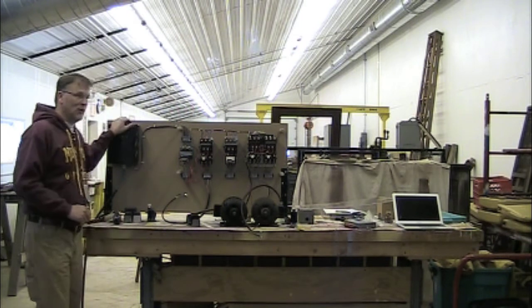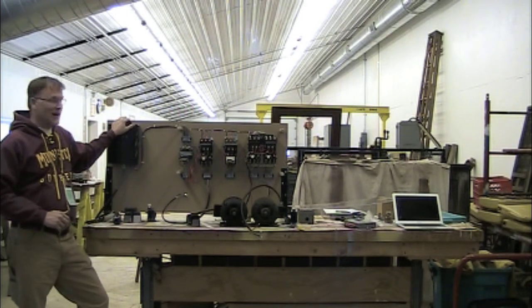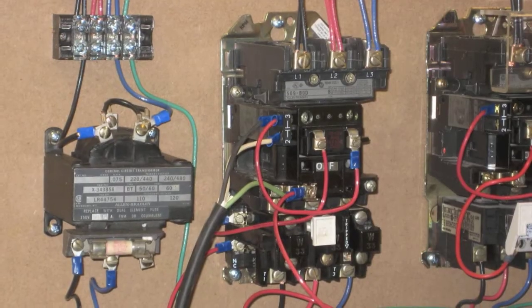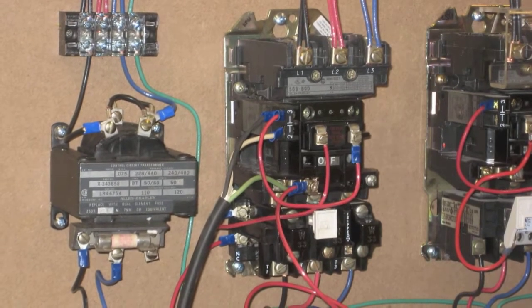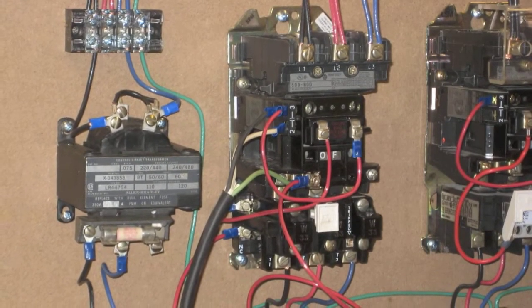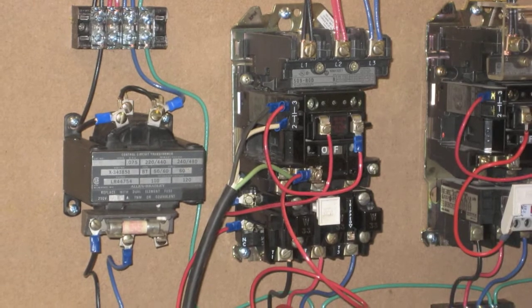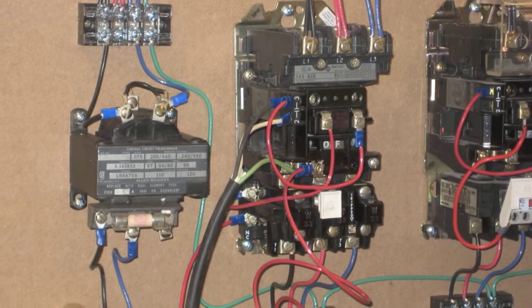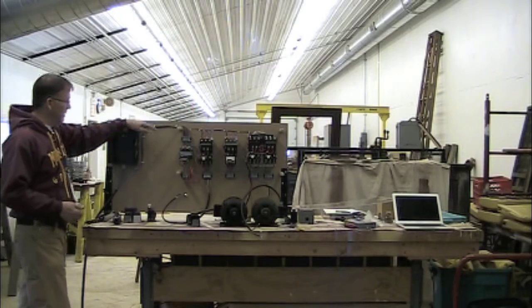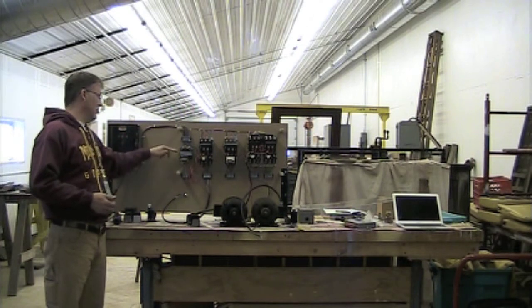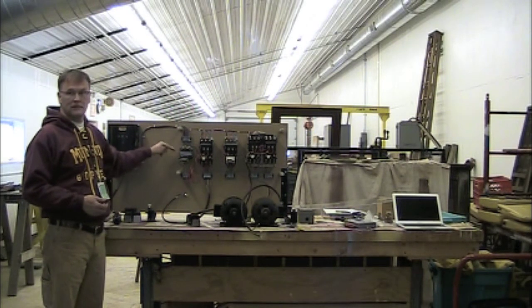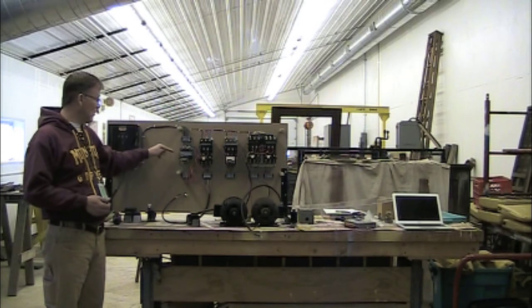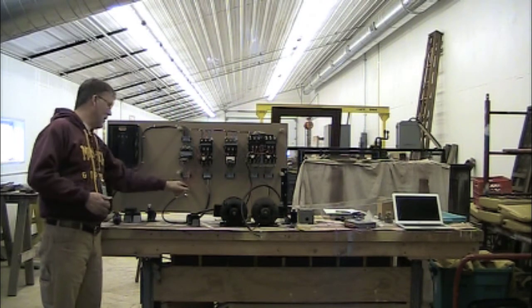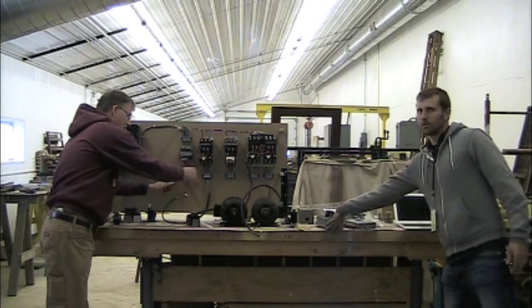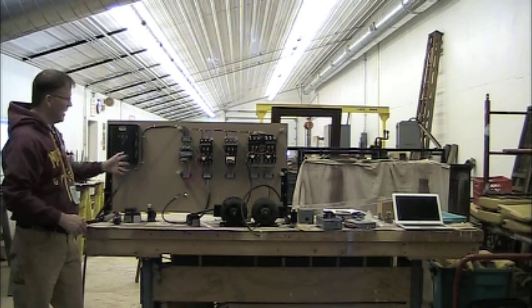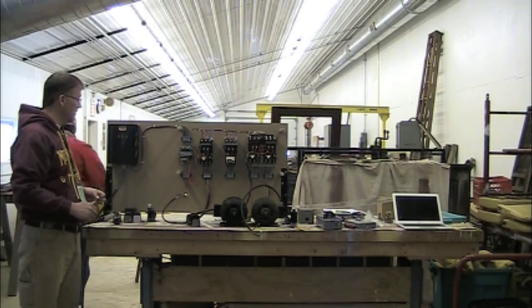These are all 120 volt coils. So that's something a lot of people run into. So I needed to have a control transformer on here because the shop here is 240 volt 3-phase. So the power's coming off of here, 3-phase power into this terminal strip. There's a 240 to 120 volt control transformer here. So I got the power coming off of there. So this is the power lead. So that's the power that we'll use to do any of these.